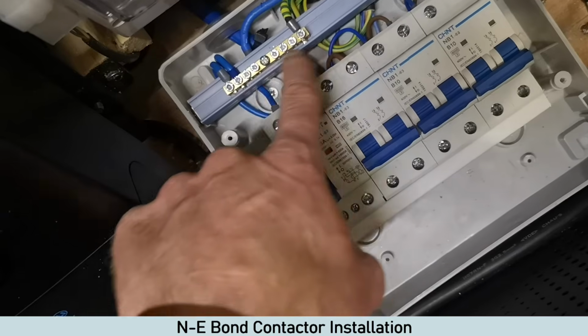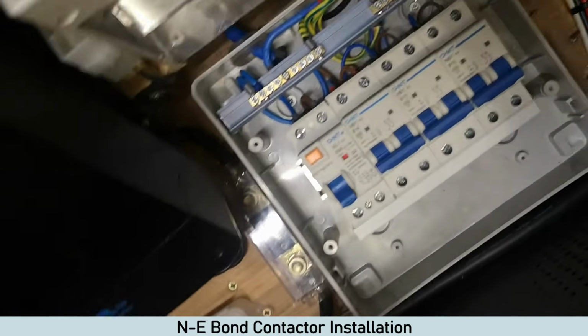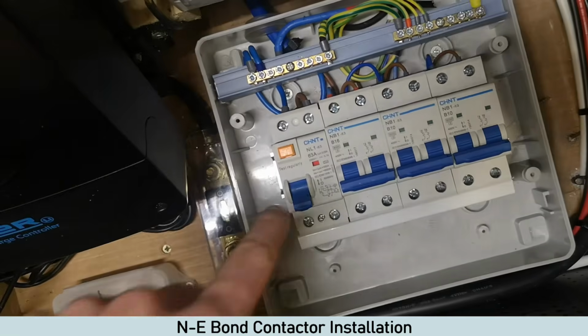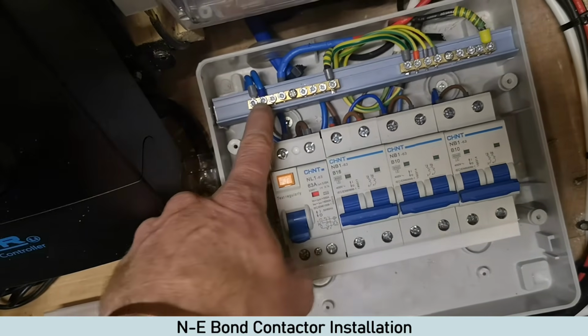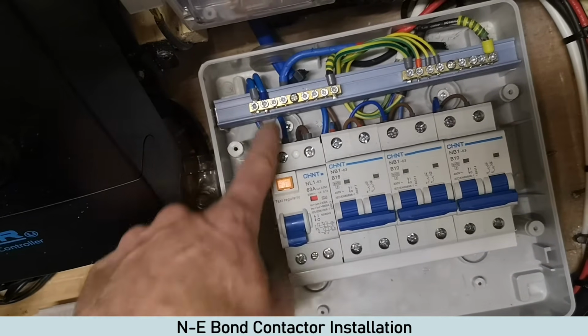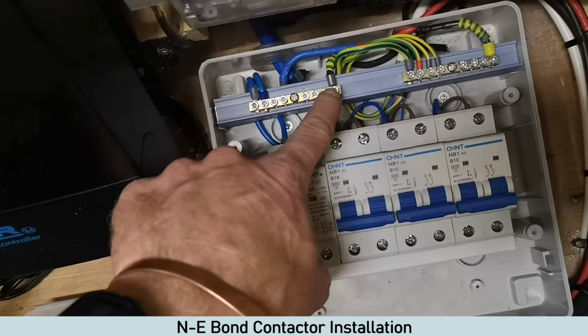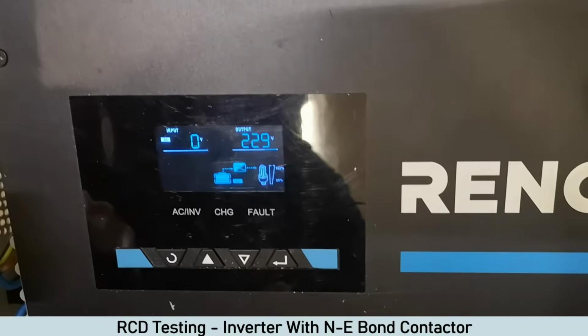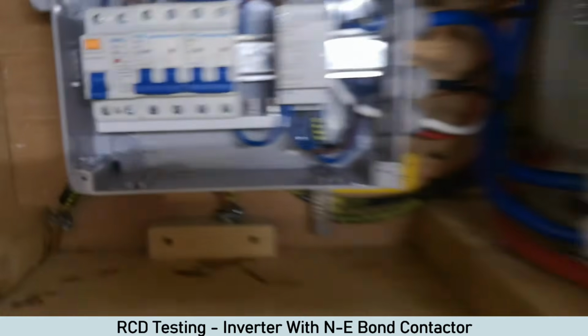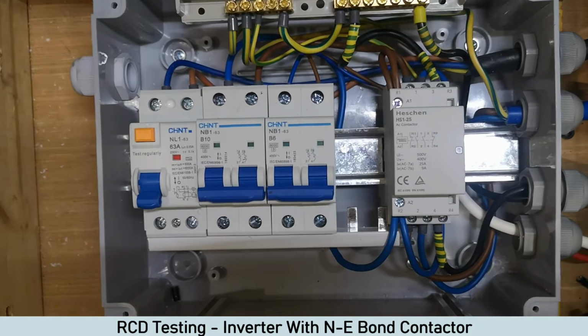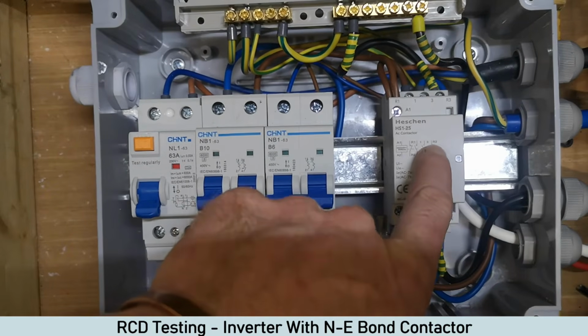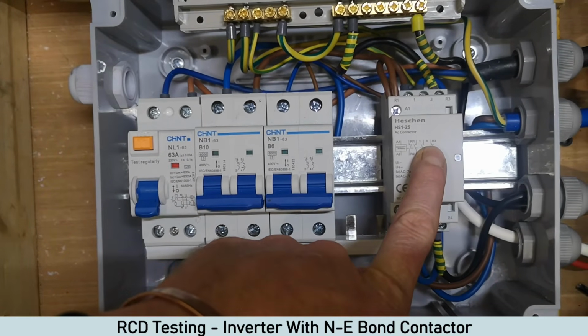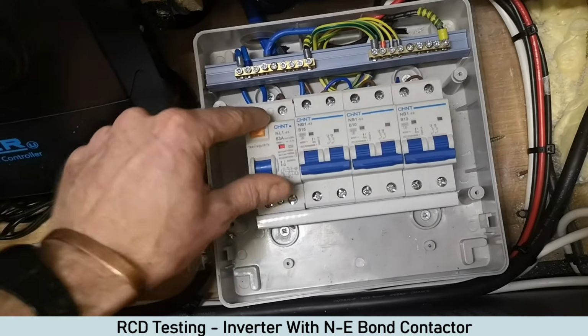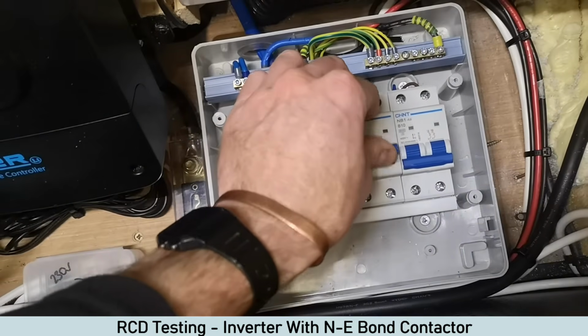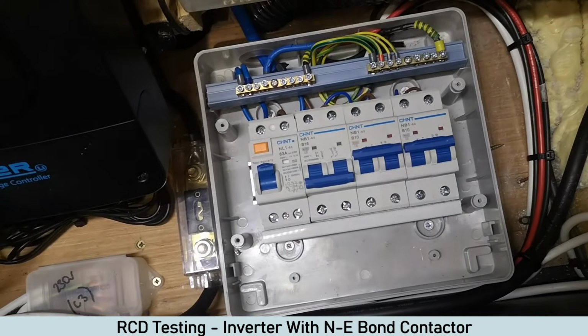So we've actually made a neutral bus bar in here for DB2. The outgoing neutral from the inverter charger comes into here, and then we've got a link from there to the RCD, which then this link goes on to. So the state it's in now is the inverter is on, the hookup is off. So currently we have the neutral to earth bond. And the way of showing you that is I will turn on the RCD and just give it a test. I'm going to put on both those circuits because I'm going to be using those now.